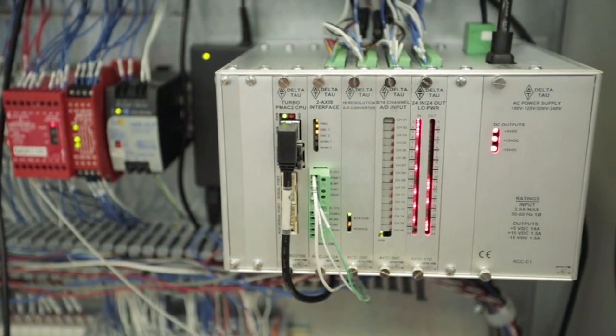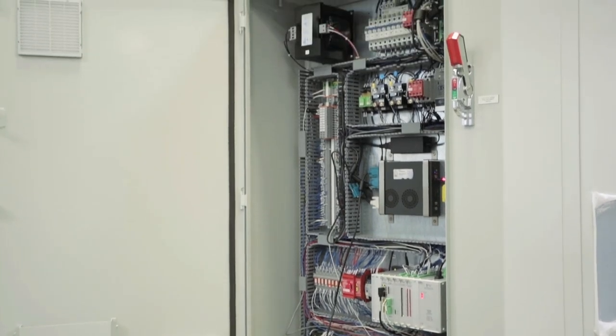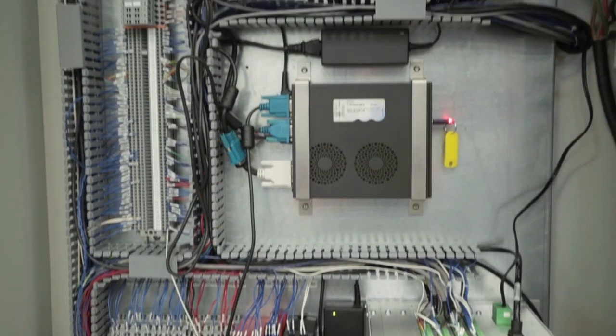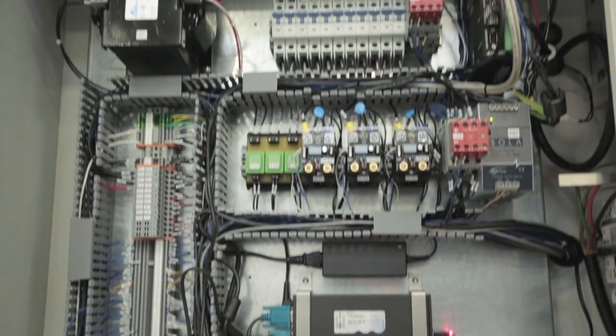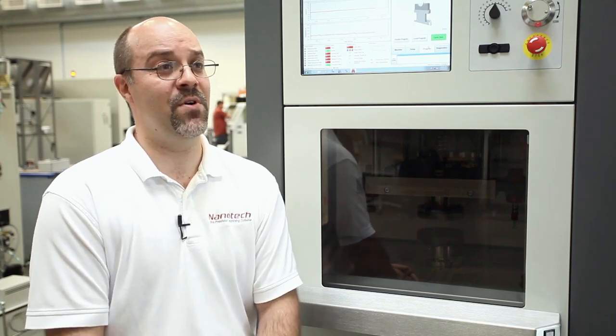We're using a UMAC, 240 MHz Turbo PMAC. We've got analog feedbacks for pressure transducers. We're reading analog for temperature sensors. We were able to take whatever feedback source, cascade loops, wrap loops around it, and the beauty of the UMAC control is that it will handle all of that stuff.